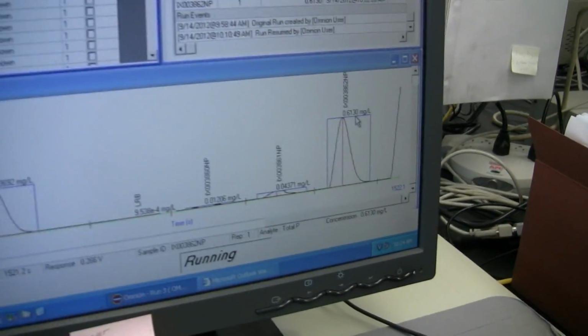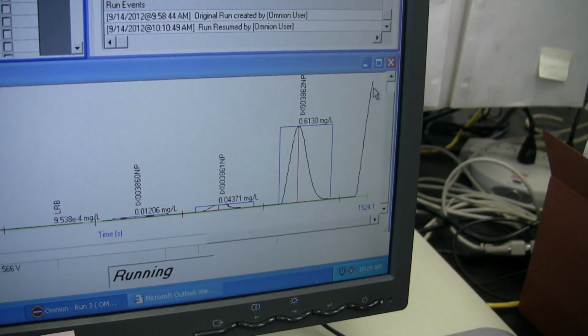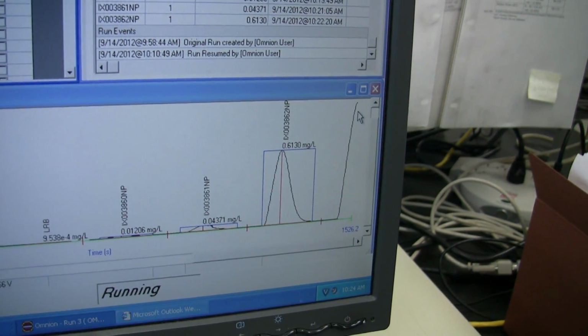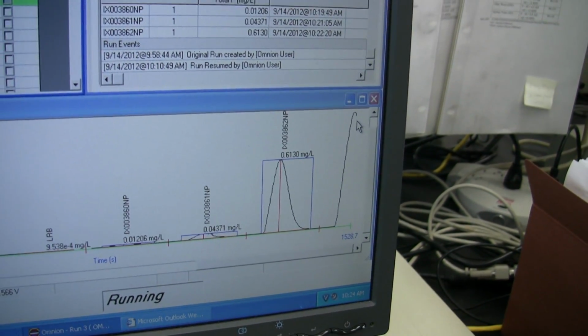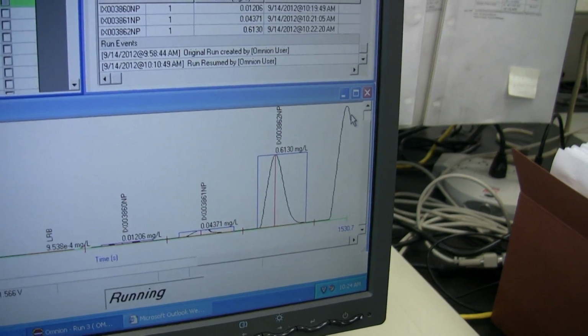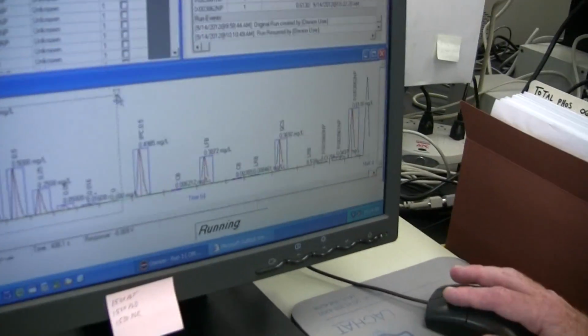But there, for example, this one is actually 0.6, and this one's starting to scare me, because if that goes over 1 part, I have to do a dilution. Because my highest standard is 1, I can only report out numbers that are within my calibration range, so I might have to do a dilution on that one. That would mean this has more phosphorus in it than you expected? It's going to be just under 1, it looks like. So I won't have to do a dilution.